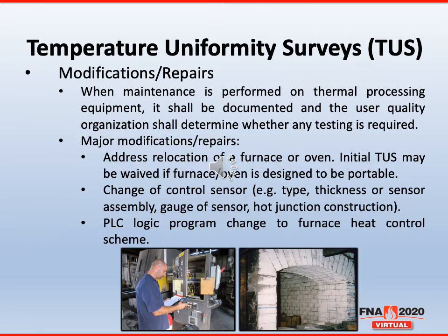So some of the changes we made also to major modifications or repairs. We addressed if you relocate a furnace or an oven. An initial TUS may be waived if the furnace or oven is designed to be portable. There were a lot of misconceptions. If an oven or furnace is moved from one location to another, it automatically required an initial survey. But there are many manufacturers of furnaces and ovens now that put them on wheels so they can be portable. But it will be up to the quality assurance organization to determine if an initial survey or some sort of periodic test may need to happen prior to putting it back into production.